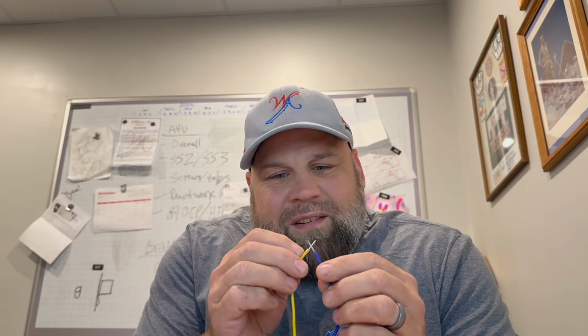We verified that. She said she did not. So when she was taking out those wires, at one point, she touched the positive 24 volts to the common and spark, pop, there goes the fuse. She put on the thermostat, got it all wired up, and voila, no power to the thermostat. She assumed it was bad. She did that 2 more times before calling us to come out there. So easy peasy. Just interesting that she didn't state that she tried to change that thermostat 3 times today already, but that's okay.